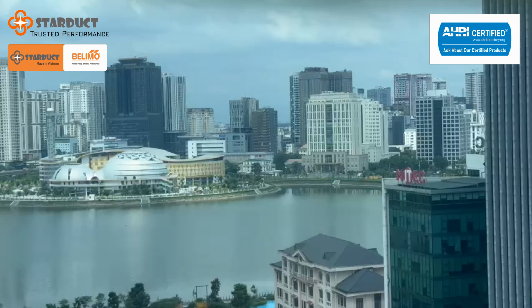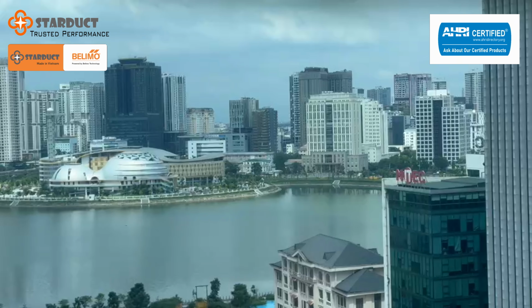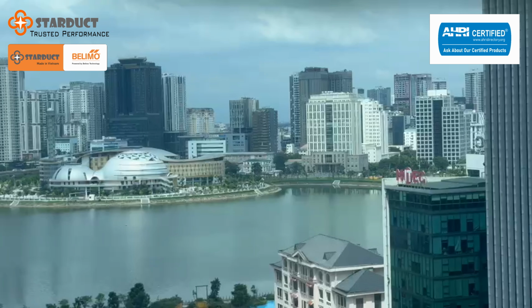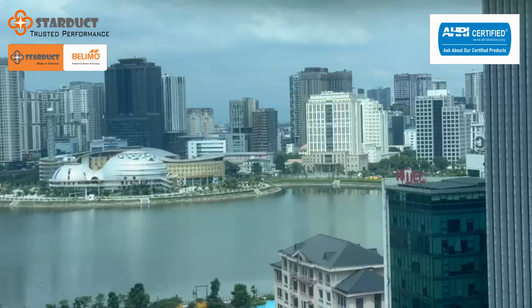So field calibration, as outlined in sections like 5.3 or 8.3 of typical manuals, isn't just a nice-to-have check. It's a required process where the TNC team, the testing and commissioning team, must use a flow hood or a balometer. They compare that physical measurement to what the BMS is displaying, and if the difference is more than, say, 5%, which isn't a huge margin, then adjustments have to be made. And sometimes that adjustment isn't just tweaking settings, it might involve adjusting the K factor itself or looking deeper at the delta P components to make the reading match reality.